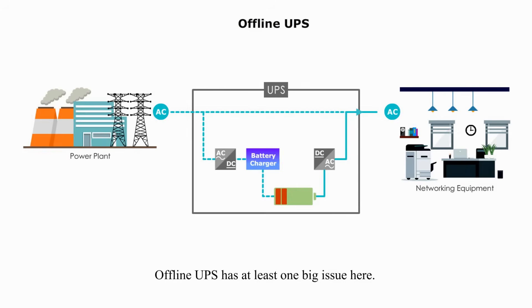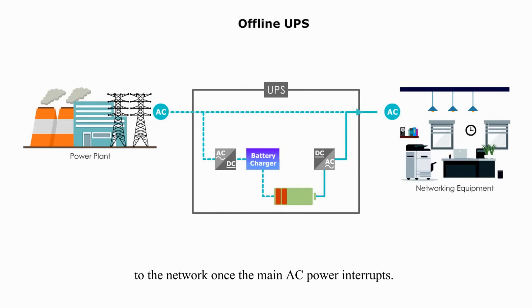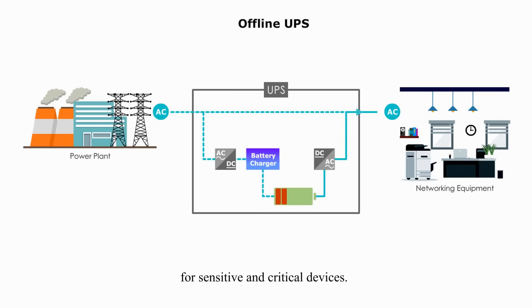Offline UPS has at least one big issue: it has a switching delay to supply power to the network once the main AC power is interrupted. Therefore, offline UPS is not recommended for sensitive and critical devices.